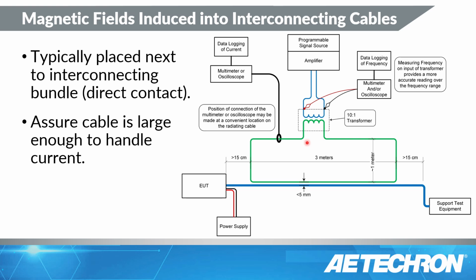Now, remember that you're going to have a lot of wire here as a result, because not only do you have, say, 3 meters of exposed wire, but you also have to move these wires back a meter on each end. So there's 3 meters, 4, that's got to come all the way back to the transformer and out, so that's another 3 meters and another meter here. Well, that's 8 meters now of wire. And if you do 2 turns, you're doing that twice. That's 16 meters of wire. That can create a lot of impedance. There's a lot of wire impedance. So if you end up with only needing 1 turn, don't coil this wire up down in the corner.